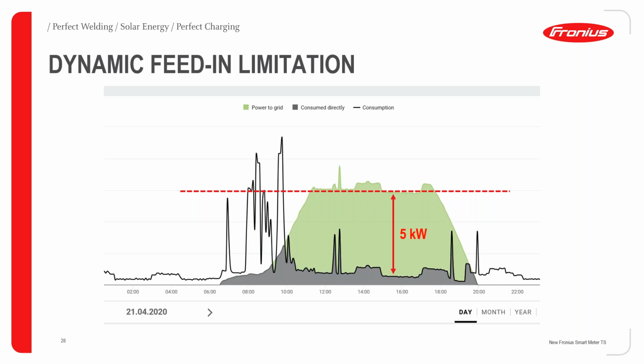Then you cannot simply restrict your system to produce only 7 kilowatt all the time, because you will lose more energy, more production then. So that's why you need to configure dynamic feed-in. Based on the consumption, this feed-in will always be adjusted. The inverter will make sure that the feed-in does not exceed the value you mentioned here.